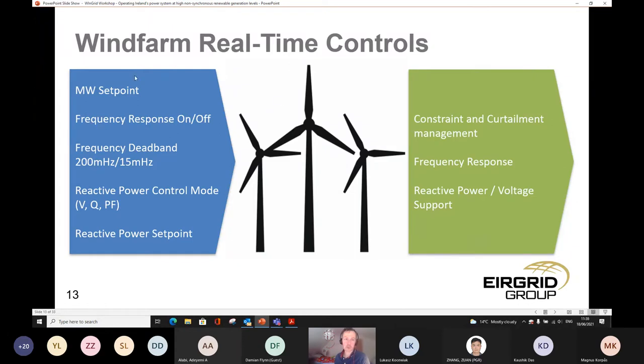So from that control, what we get is the ability to constrain and curtail the wind. When some of those system limits are hit, SNSP, or if we anticipate a rate of change of frequency issue, we can constrain or curtail the wind to reduce the collective output of either all wind on the island or individual wind farms.